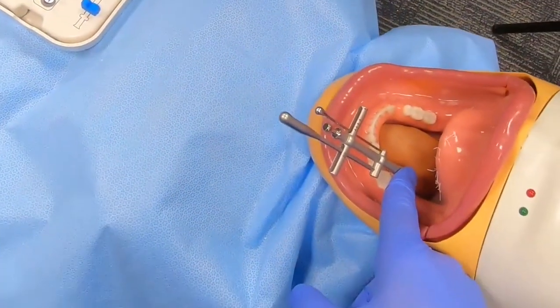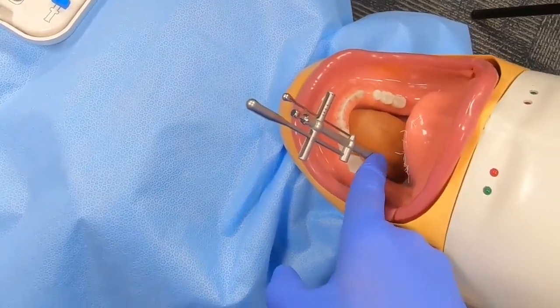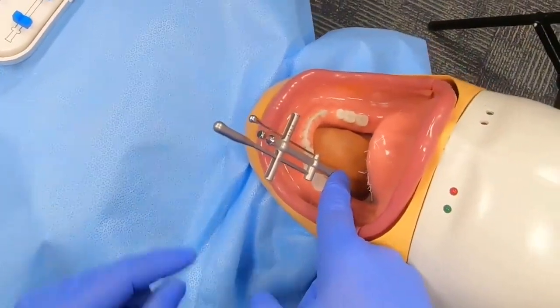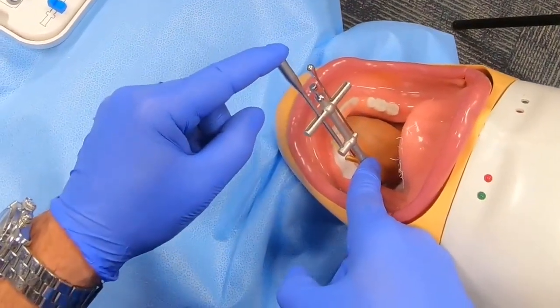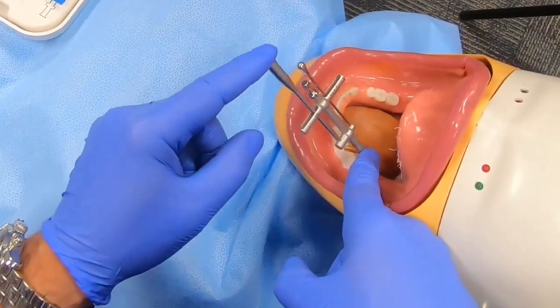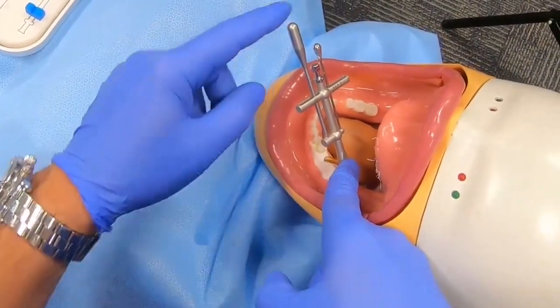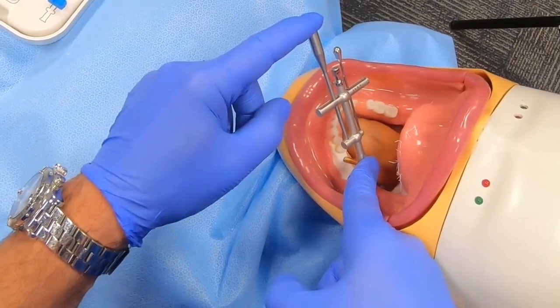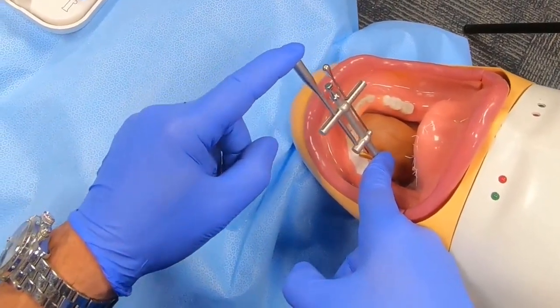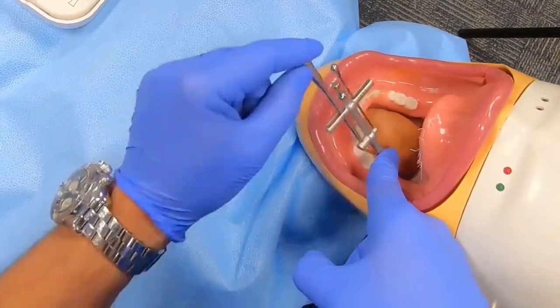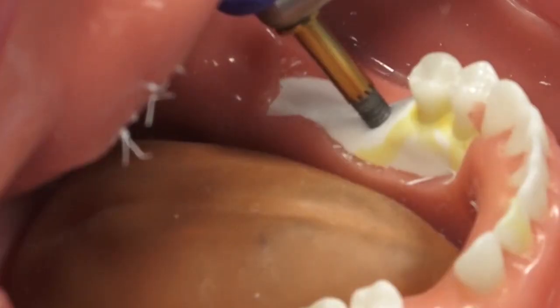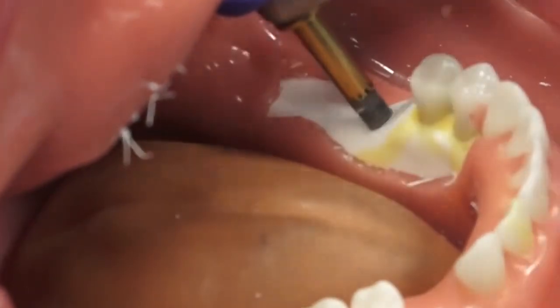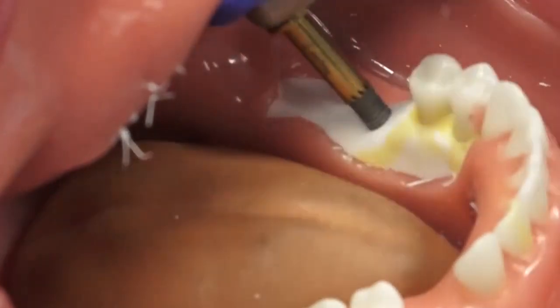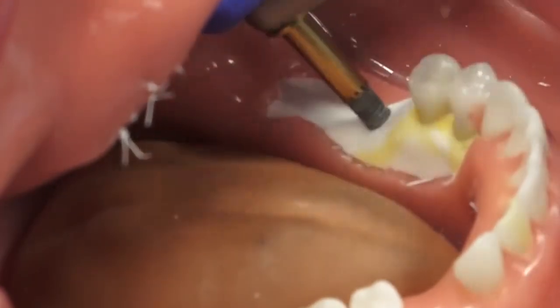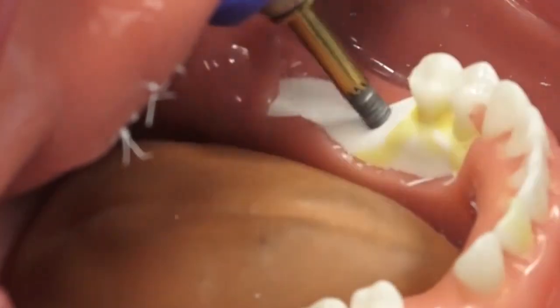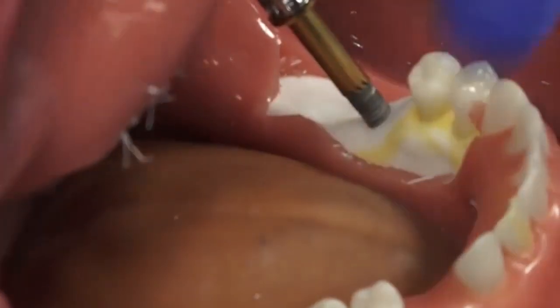And really the key, sometimes clinicians fail to remove the implant because you're really not applying a vertical pressure on that driver. And now we're just going to go there slowly. And most of the time when this implant is osseointegrated, you kind of feel a little bit of pressure as it does disengage. You kind of feel it because now it's a little bit easier to remove. And sometimes if you do not really select the right implant remover, you need to stop because otherwise you'll damage the implant. It'll become very difficult to remove. So if you're not sure, take your time until you select the right driver.